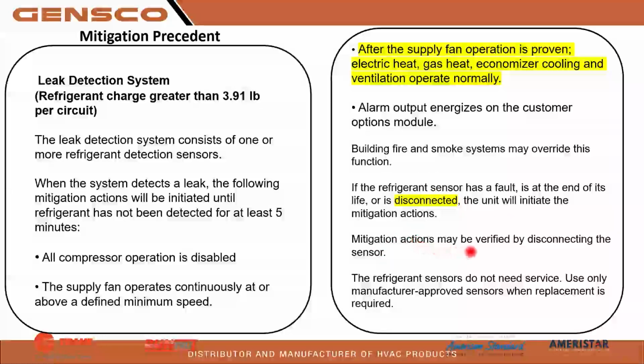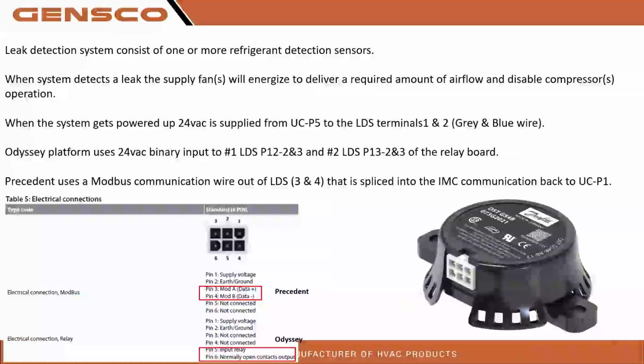Mitigation actions may be verified by disconnecting the sensor. So if you disconnect the sensor, that will activate mitigation. That's how you're going to test it. The refrigerant sensors do not need service. Use only manufacturer approved sensors when replacement is required. So that's what it looks like right there. Now in the Odyssey splits, they are going to be wired differently, but it will be the same sensor.